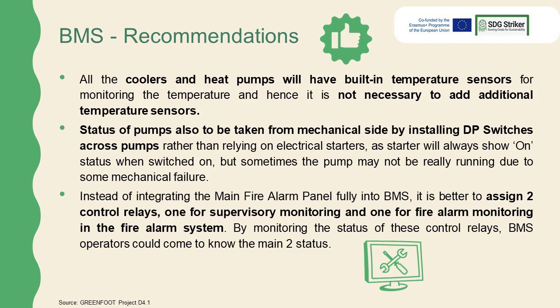To improve the performance of a building management system, all the coolers and heat pumps will have built-in temperature sensors for monitoring the temperature, and hence it is not necessary to add additional temperature sensors. Status of pumps also to be taken from mechanical side by installing DP switches across pumps rather than relying on electrical starters, as starter will always show on status when switched on, but sometimes the pump may not be really running due to some mechanical failure.